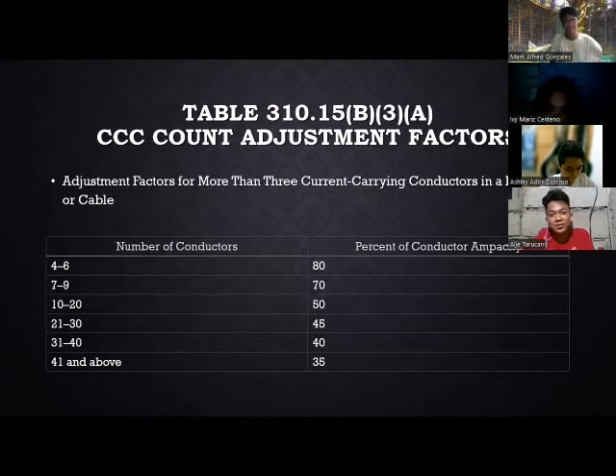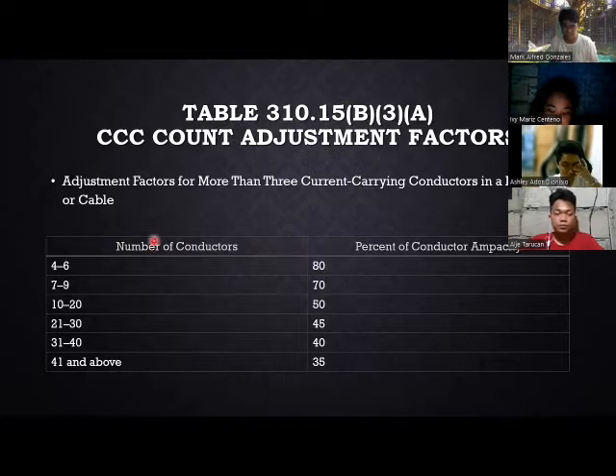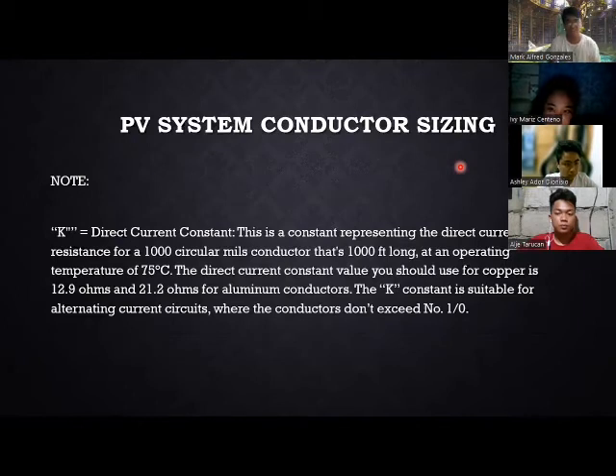So then the next table is Table 310.15(B)(3)(a), the adjustment factors. These are the adjustment factors for more than three current-carrying conductors in a raceway or cable. As you can see here, in a 4 to 6 conductor cable in a single conduit, the percentage of conductor capacity is only 80%. It goes down if there are four to six cables. The more conductors, the lower the capacity. That's it, just note that.